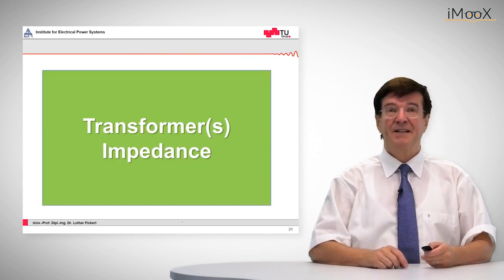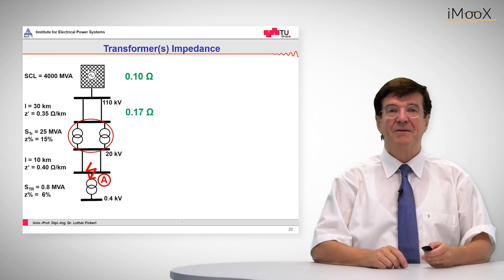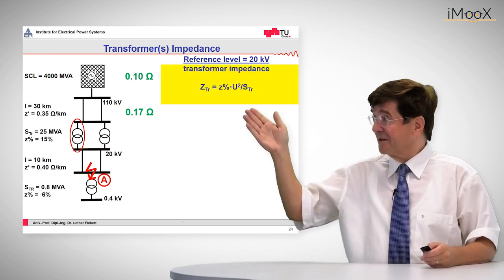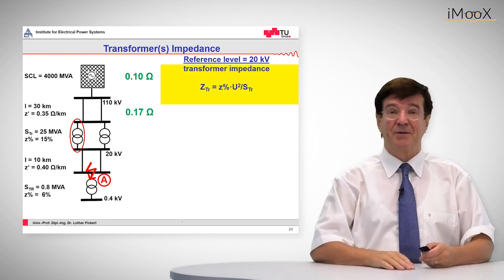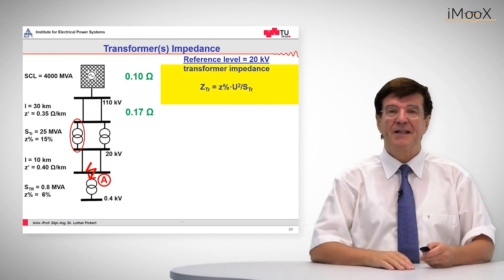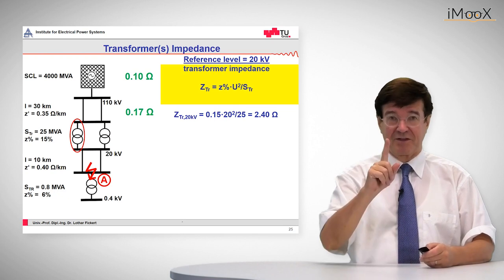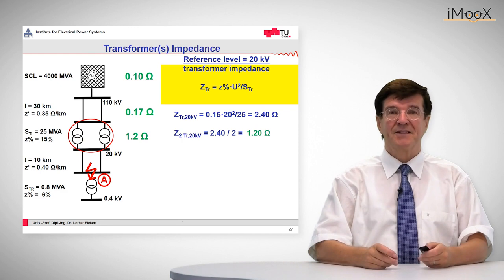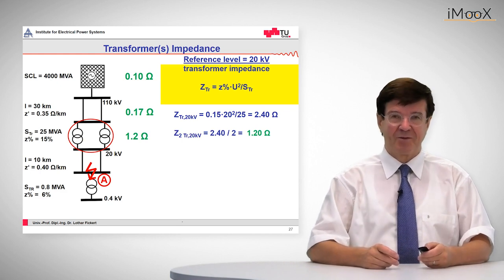Next is the transformer impedance. The transformer impedance is given by the percentage voltage times U squared divided by the apparent power of the transformer. In this case we obtain for one transformer 2.4 ohms, and two transformers in parallel is half of that. So this is the transformer impedance.